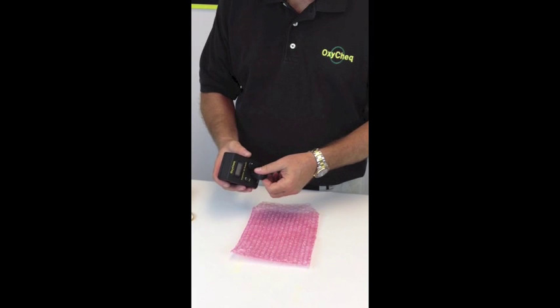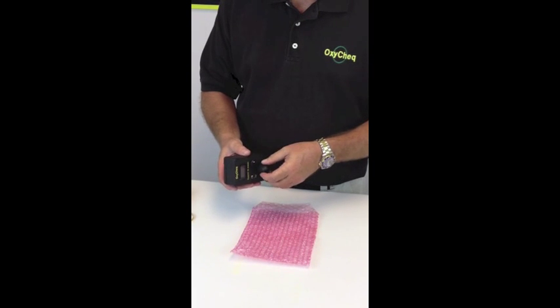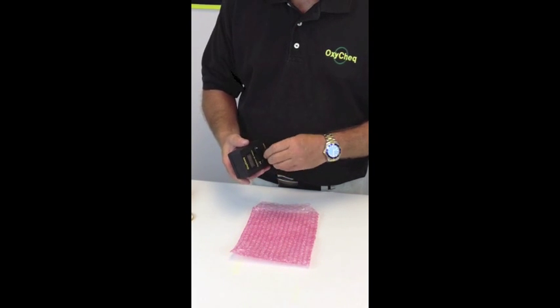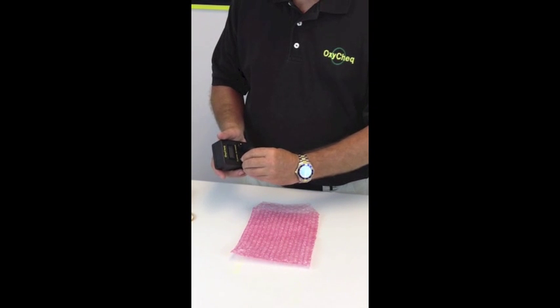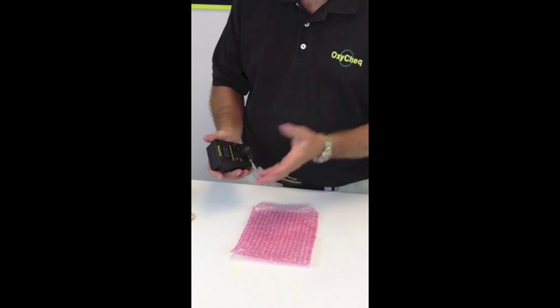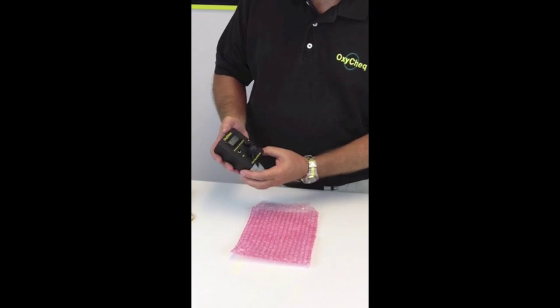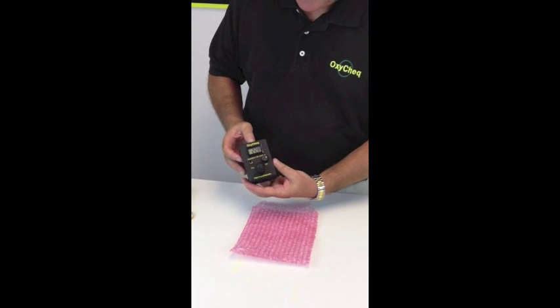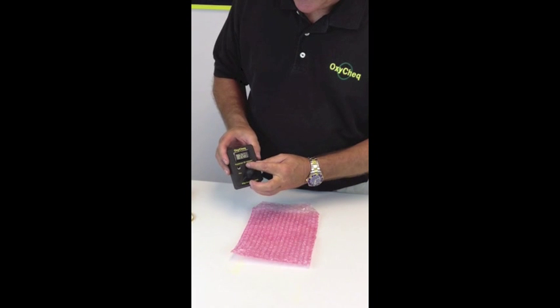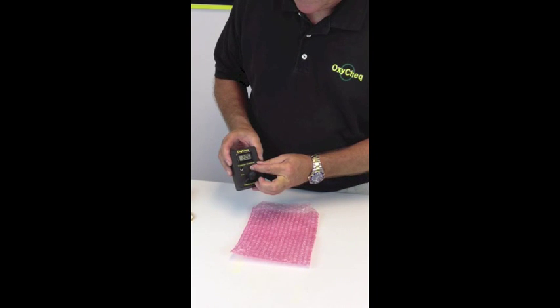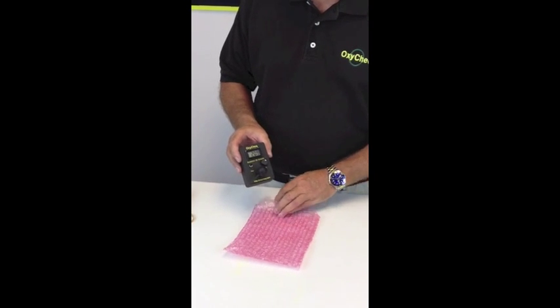Now we can take the sensor flow cap and place that on the analyzer itself. We lift up the on-off switch boot, turn the unit on, the display is functioning, and now we can calibrate it to 20.9. We're now ready to analyze gas. Your Expedition oxygen analyzer should be ready to analyze gas now.